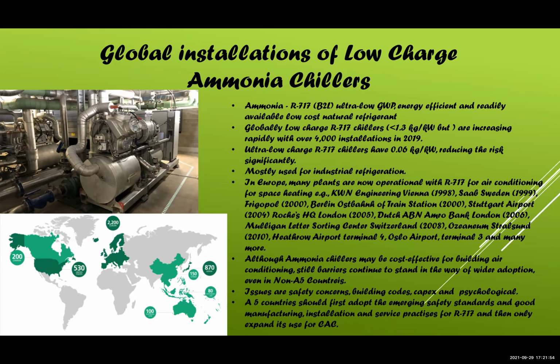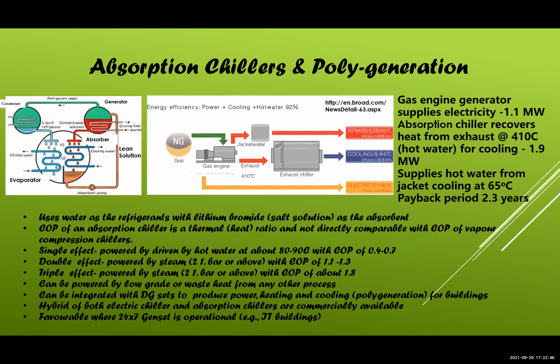Now there are many more ammonia chillers with ultra low charge, and therefore it's going to be interesting to watch. The problem in developing countries is that ammonia is still unsafe because they don't follow most of the safety regulations, and they bypass some of the international standards because they're too expensive to implement. When you compare with halocarbon refrigerants, like any other refrigerant, HFC, you will find that the cost of ammonia is much more if you follow all these international standards, because they have to follow the standards. And these things happen, and therefore ammonia is still going to be an issue.